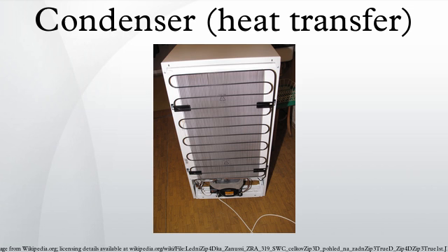A typical configuration of such a condenser unit is as follows: the heat exchanger section wraps around the sides of the unit with the compressor inside. In this heat exchanger section, the refrigerant goes through multiple tube passes, which are surrounded by heat transfer fins through which cooling air can move from outside to inside the unit.